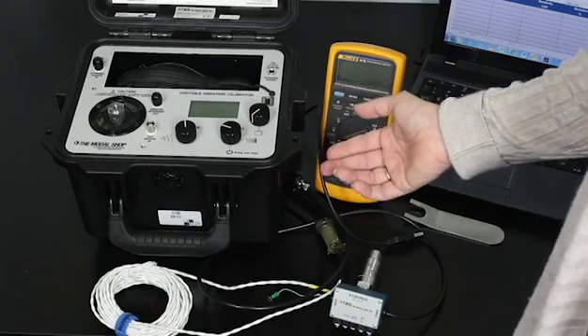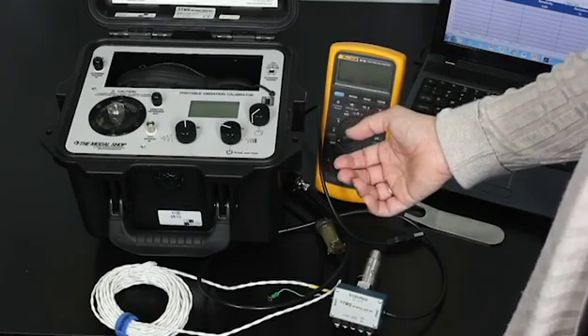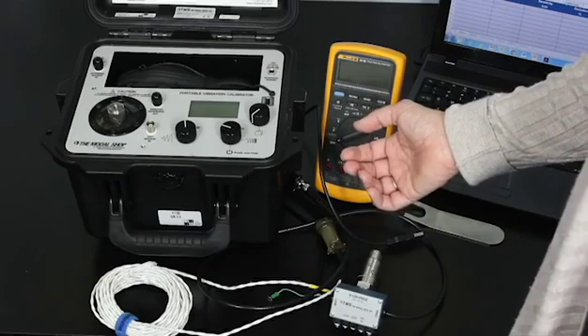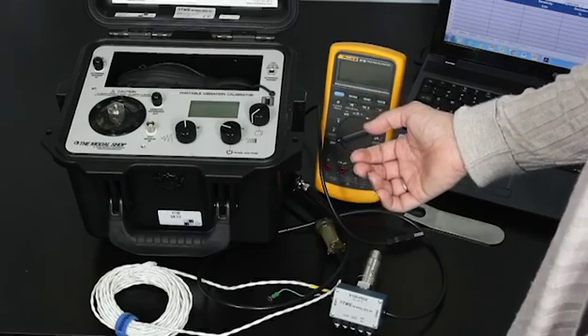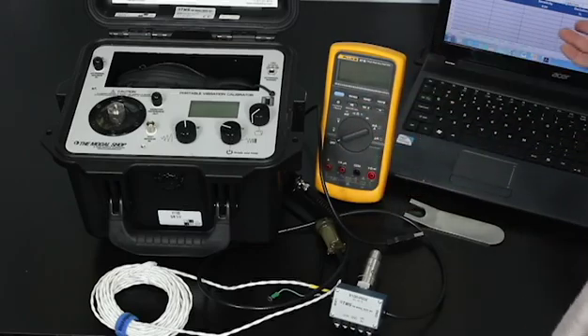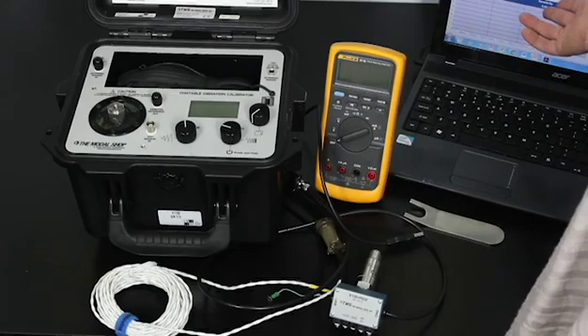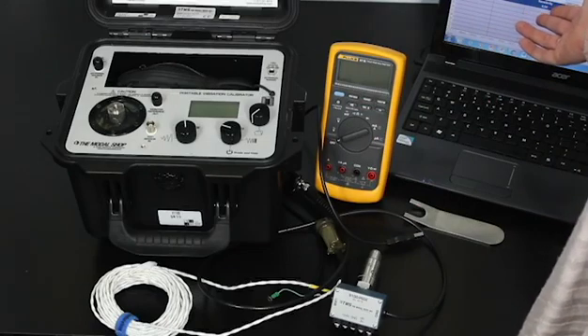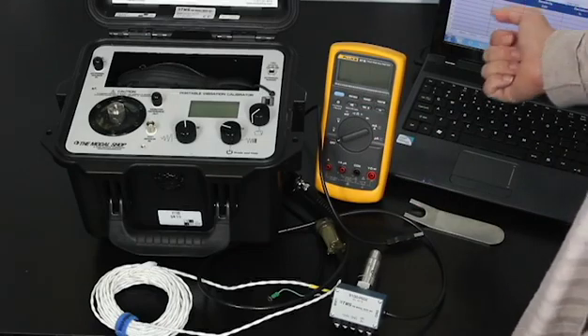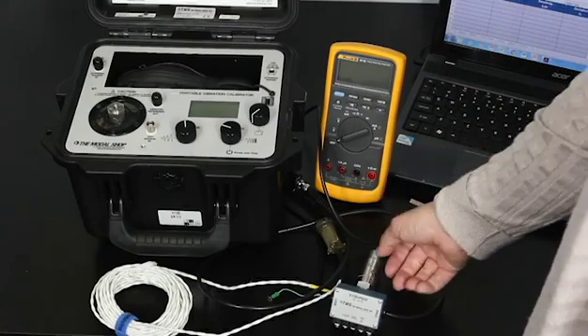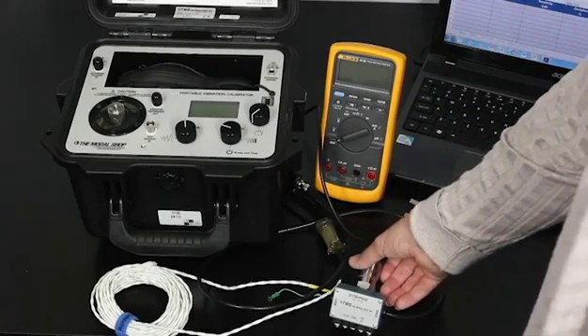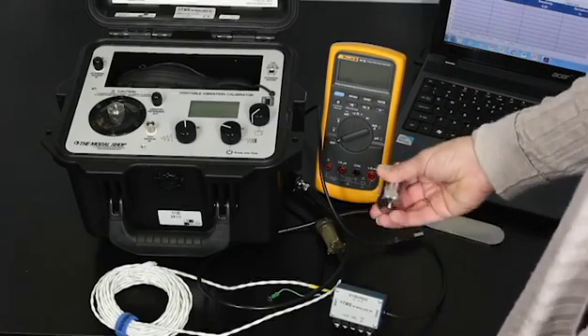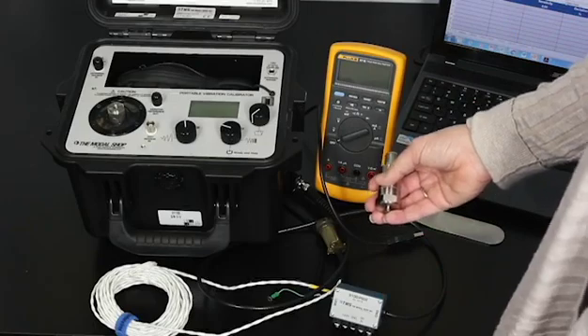We'll be testing our sensor at several test points, and after each test point we'll record the output current into the report generation workbook, which is supplied with the portable vibration calibrator. This will allow us to determine if the sensor is exhibiting its expected linear response and if it's reaching its full-scale output. So let's set up the test.